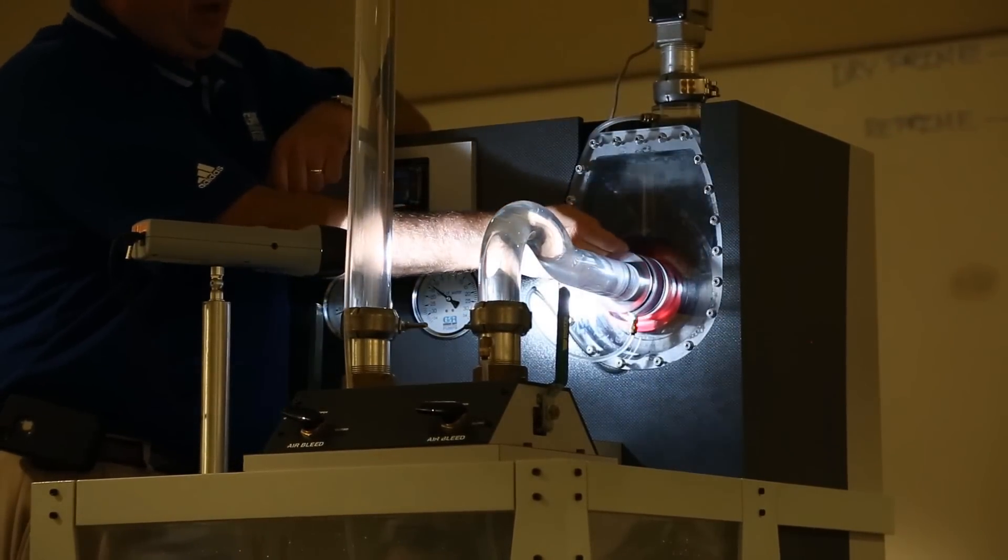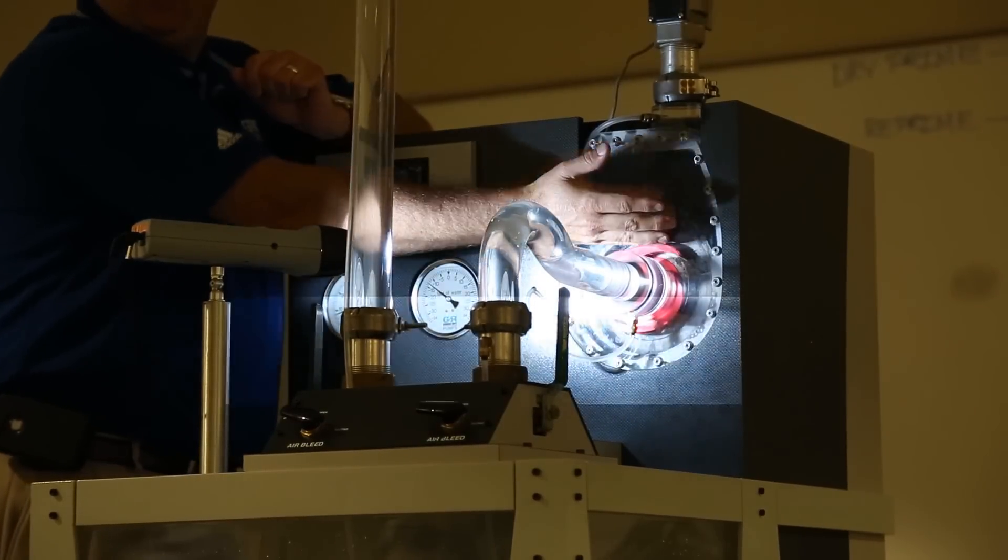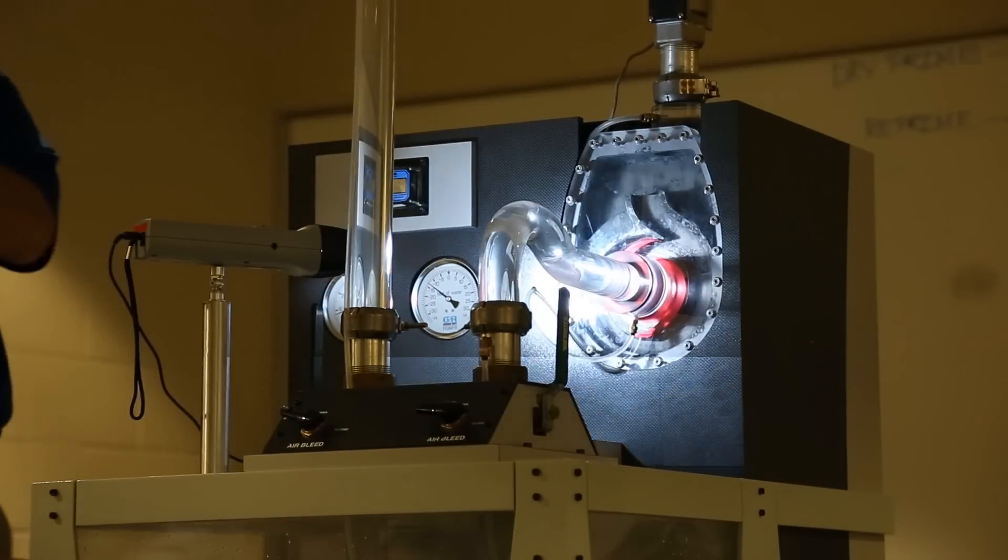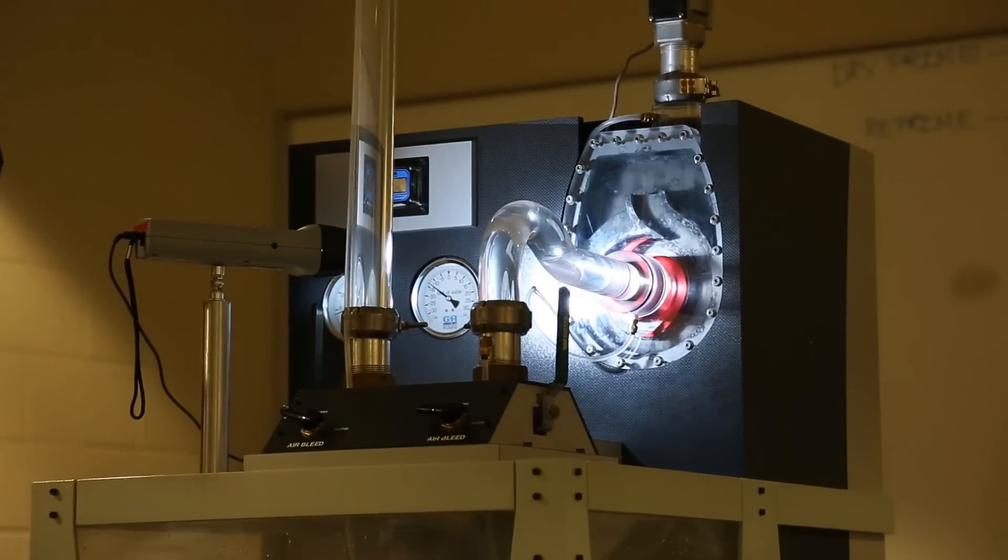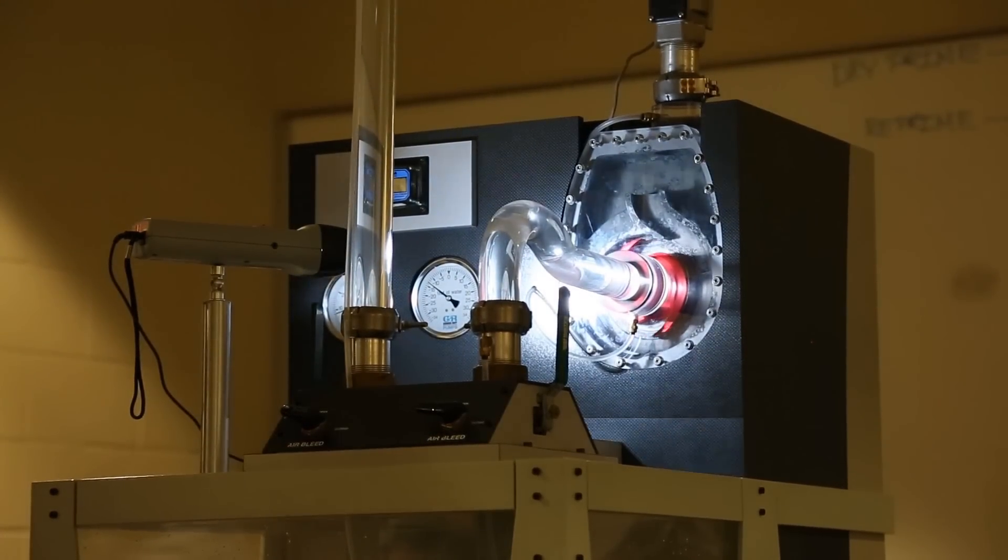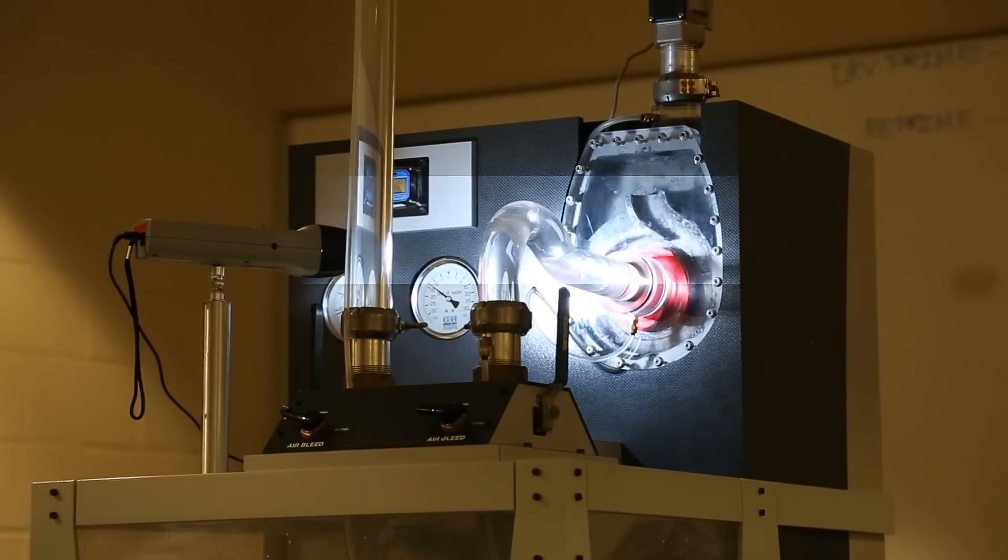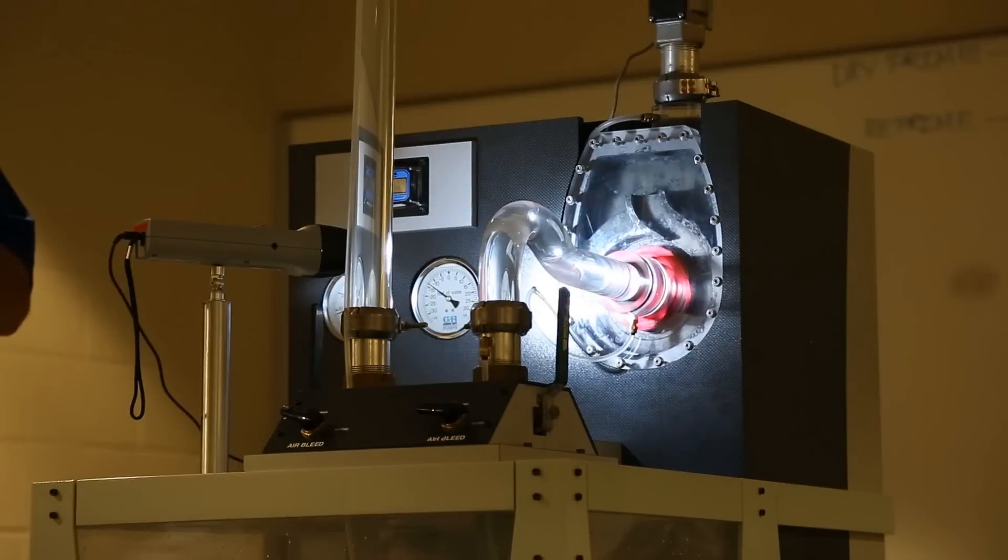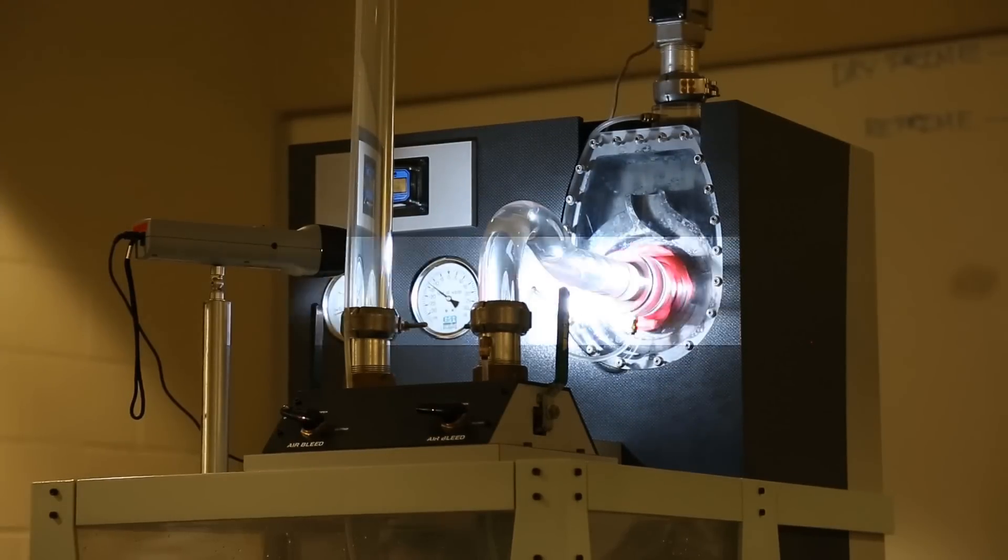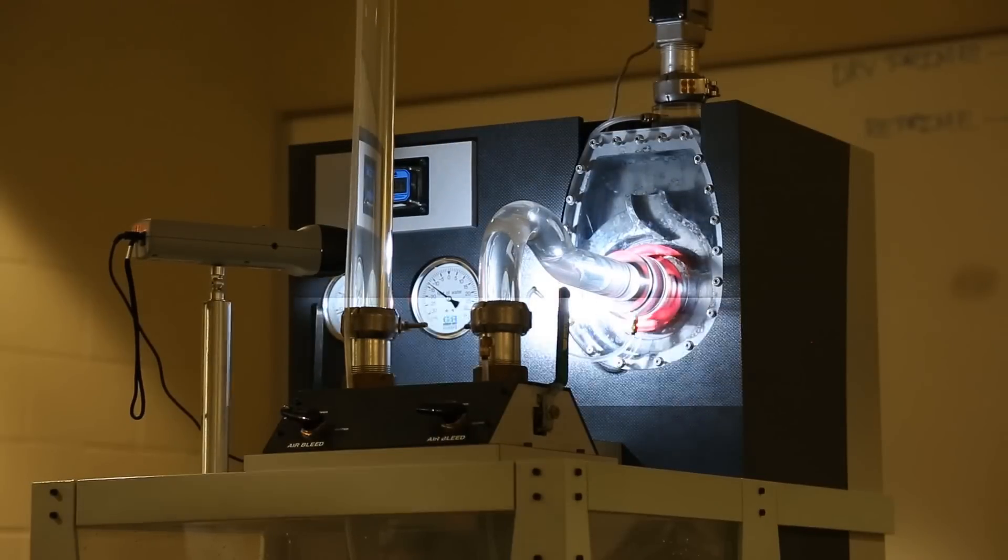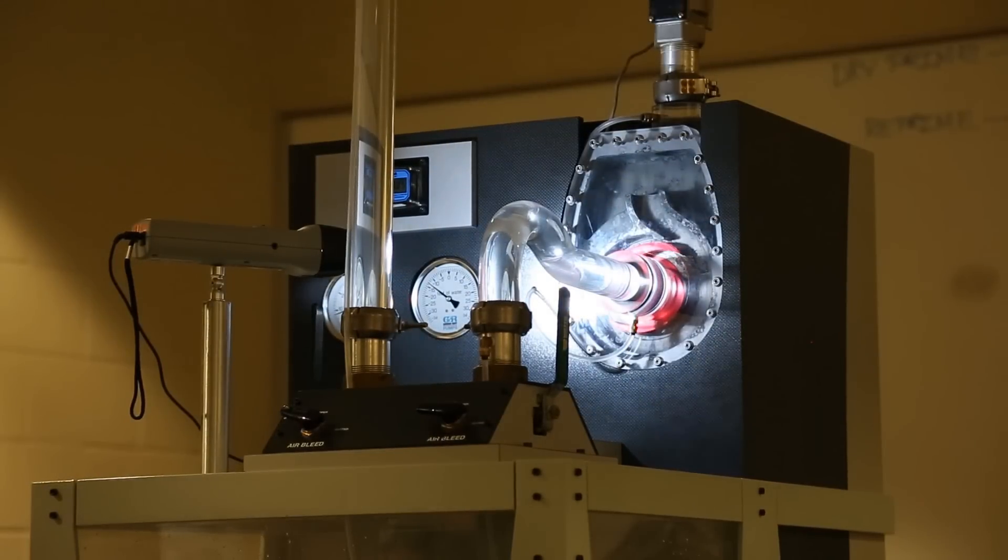As I get to the eye of the impeller, on the discharge side of this pump there's no restriction. So all of that liquid slows back down and those vapor bubbles implode back into liquid. And that's where the destructive force of cavitation is, when those vapor bubbles implode back into liquid. They give an energy discharge that's been measured between 80 and 110,000 PSI of energy release.